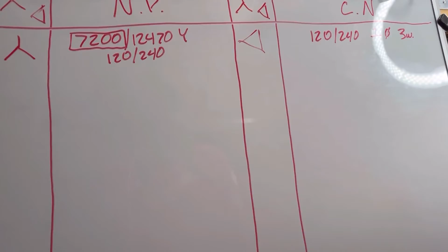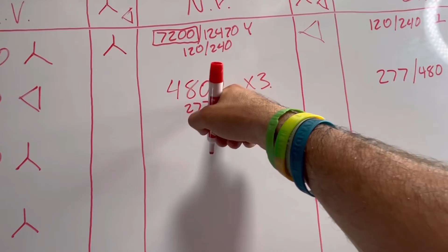So my nameplate, let's say it says 4800, and let's say, I don't even know, 277. So primary input 4800, 277 volt output. My customer needs, let's say, are 277/480, 3-phase this time, 4-wire. So there are 3 transformers here, right? This is the nameplate for all 3 of them. So again, remember the little hack. If this number matches this number, it's going to be a delta. So 4800 volt input, 4800 phase to phase, those 2 numbers match, delta hookup.